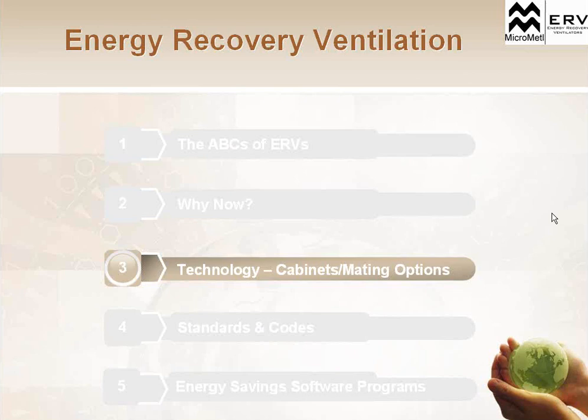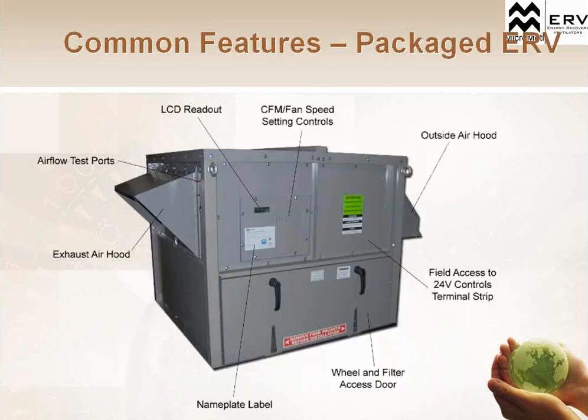So we talked a little bit about the technology of the wheel itself. Let's talk about the cabinets and mating. How do we get this energy recovery system to mate with the HVAC system? How does that actually work, and where do we get our ducting and everything? Here's a picture of a typical packaged roof-mounted energy recovery ventilator, an ERV section. Right here we have the wheel laid on its side, so the wheel is flat in this space. It would actually slide right out right here. This cabinet would open up.